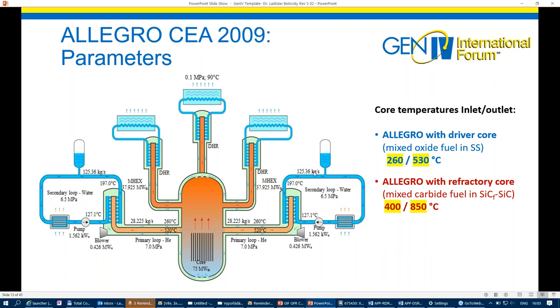Here you can see the secondary circuit composed of water and the secondary circuits of the decay heat removal loops consisting also of water. It is important to say that the power density of both concepts is around 100 megawatts per cubic meter, which is well more than one order of magnitude, maybe 20 times more than in graphite moderated helium cooled reactors like HTTR or others.